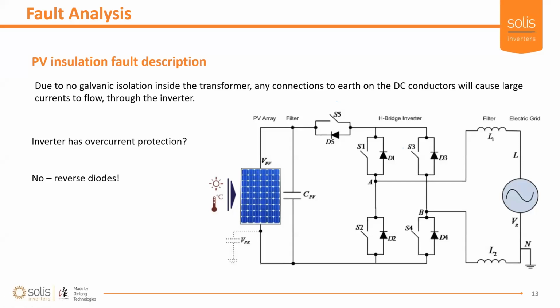Yeah, so I have seen before when connections have been made while the inverter is running on the DC side, and large currents flow, and it has caused circuit breakers to trip, flash across circuit breakers, very, very scary stuff, which of course we can understand would cause damage to internal components. So our IGBTs inside the inverters, this current flows through this whole circuit, so you will see damage on IGBTs. Each inverter has really, really good trial and tested overcurrent protection, short circuit protection, which you would think should protect against this high current phenomenon that I've just spoken about.